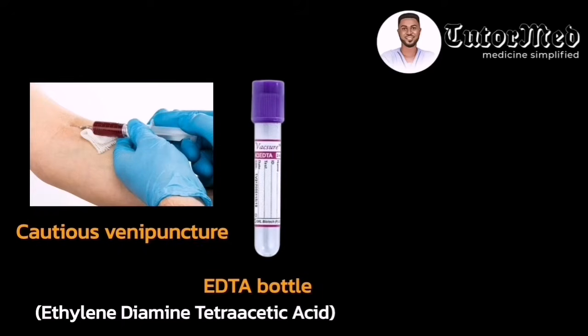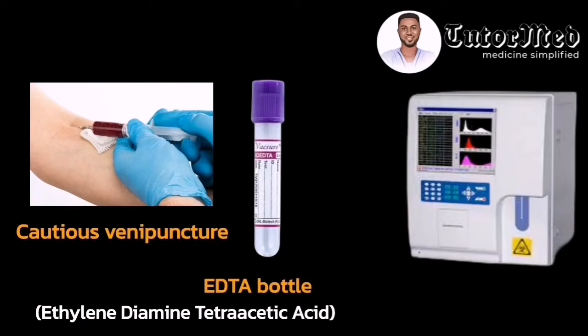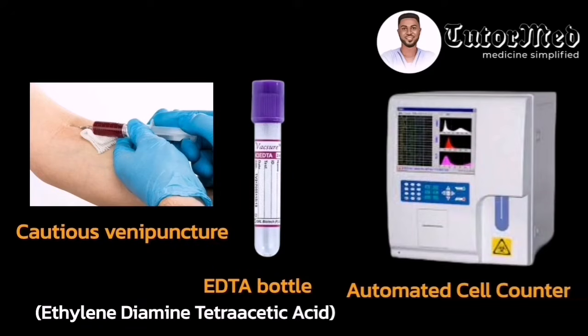This sample is then analyzed by the automated cell counter or the hematology analyzer. The analyzer just takes a small quantity from the specimen bottle and analyzes it. Then, after analyzing it, it shows the profile of the patient's blood cells, the patient's RBCs, WBCs, and then platelets.